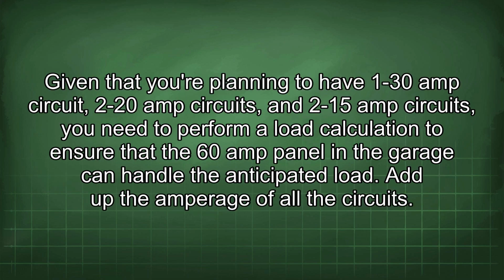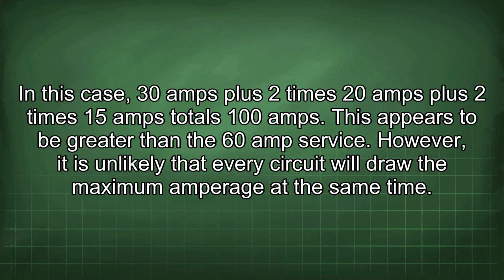Given that you are planning to have 1 30-amp circuit, 2 20-amp circuits, and 2 15-amp circuits, you need to perform a load calculation to ensure that the 60 amp panel in the garage can handle the anticipated load. Add up the amperage of all the circuits. In this case, 30 amps plus 2 times 20 amps plus 2 times 15 amps totals 100 amps. This appears to be greater than the 60 amp service.